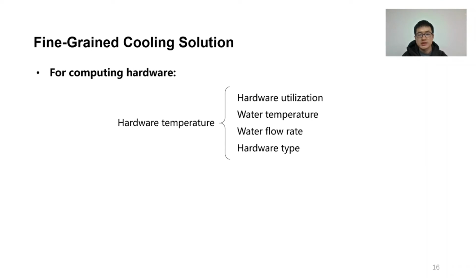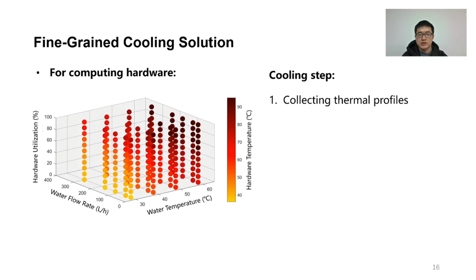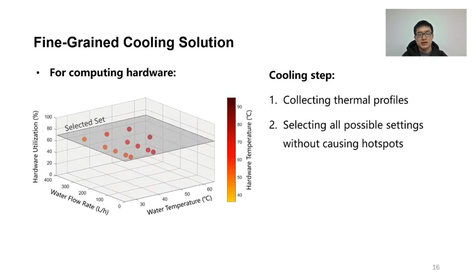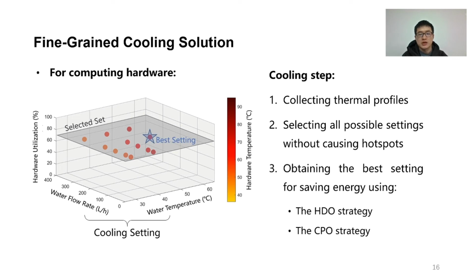Based on the cooling strategies, we devised a fine-grained cooling solution to customize the best cooling setting for each type of heterogeneous hardware components. For the computing hardware including the CPU and GPU, the hardware temperature is determined by the real-time hardware utilization, water temperature, water flow rate, and also the hardware type. Based on this observation, the cooling solution first collects all thermal profiles in advance. Then, it selects all possible settings that keep the hardware temperature below its safe operating temperature at runtime.